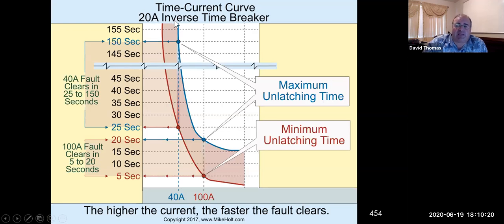Here we have a 20 amp inverse time circuit breaker, and what it says is the higher the amperage, in this case we have 100 amps, the quicker it trips. So I'm looking at this point here and this point here. So we have a minimum and a maximum reaction time of the breaker.